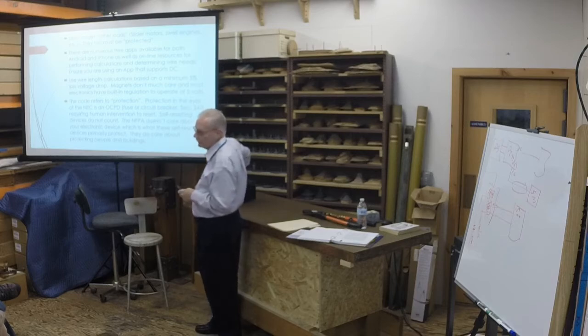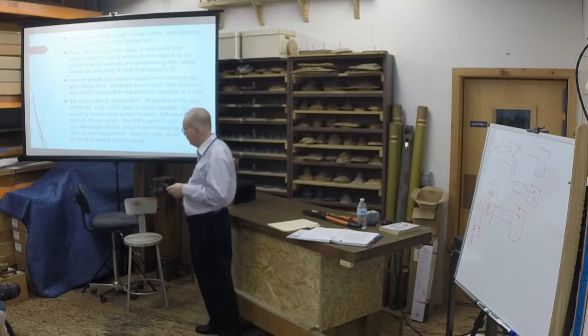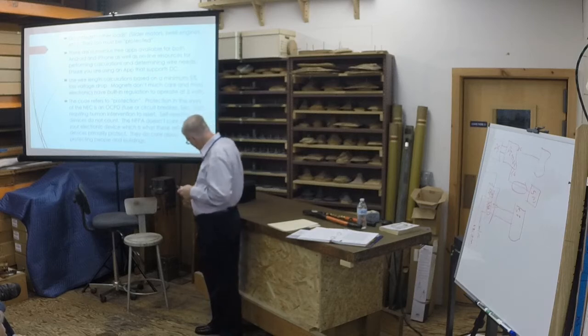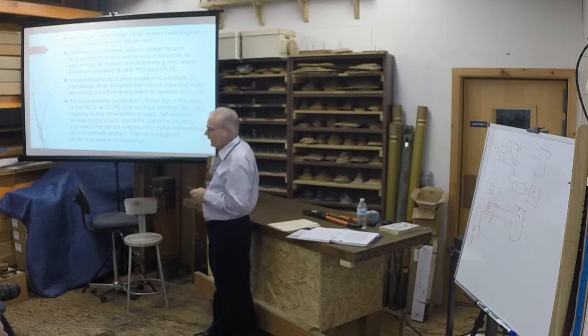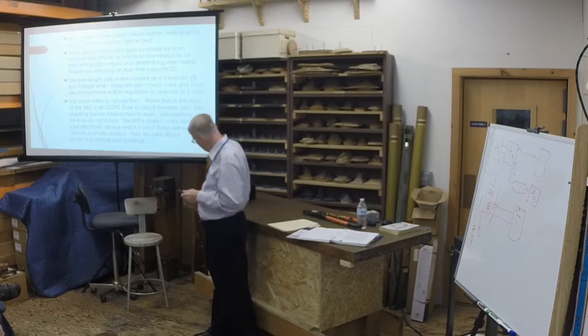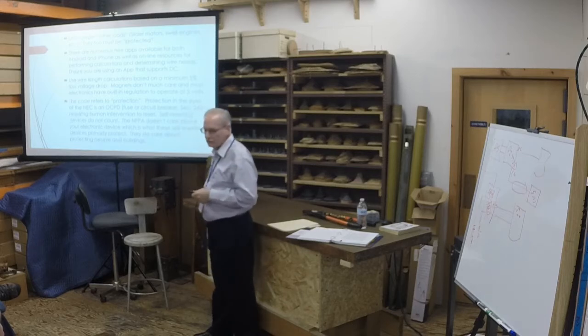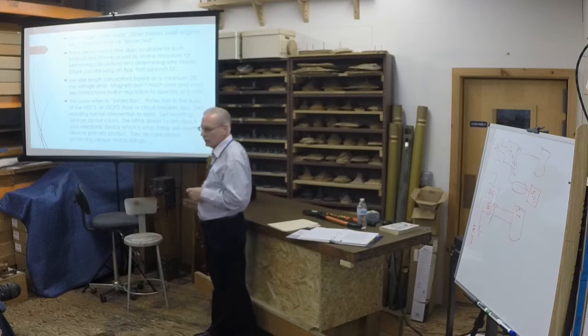Pretend this is a 55 amp. I didn't have a 55 amp sitting in my office. That's an 8, that distance, that'll actually do 60 amps. Maybe run a calc on it. That's a 10, that distance, that'll easily do 40 amps.